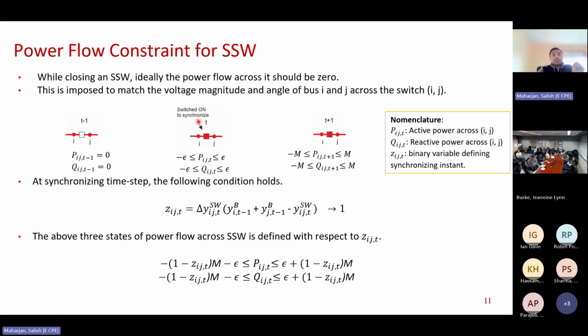So at the time of synchronization, or at the time of closing the switch, if we can ensure the power flow between these two buses is sufficiently small, then we can say that the voltage and angle between the two buses are sufficiently close. And once you synchronize them, we should allow the power to flow between these two buses after the synchronization. So the condition of power flow in the synchronizing switch is dependent on the synchronizing instant. At the synchronizing instant, the power flow should be constrained to be sufficiently small, and after that, it should be relaxed, right? So that's why we need to find out the synchronizing time step.